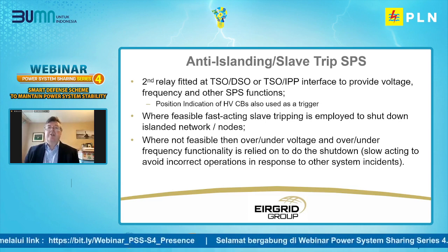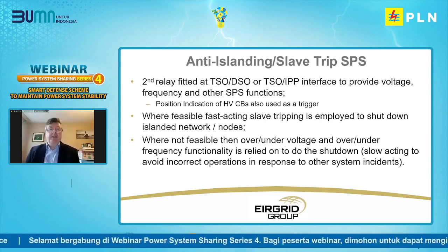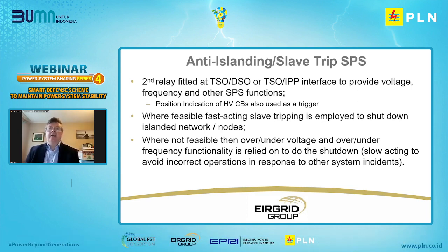To do this, a second relay is fitted at the TSO-IPP interfaces to provide voltage, frequency, and other SPS functionality. Position indication of HV breakers is also used as triggers, fed into the relay. Where feasible, fast-acting slave tripping is employed to shut down the island or network node. Where this is not feasible, under and over voltage and under and over frequency functionality is relied on to shut down islands, which is slower acting because it's more difficult to distinguish between a fault in the system and a genuine islanding event. Next slide, please.